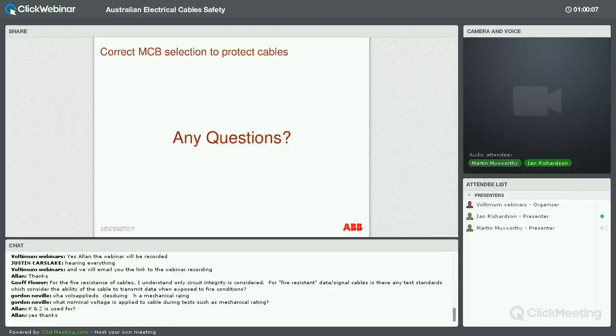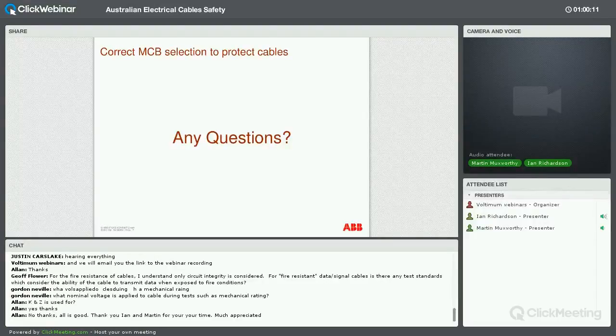Well, people are thinking, Ian, when you were talking about the reduction in life when you increase temperature, there's a rule of thumb that relates to that issue: for every 10 degrees that you increase the operating temperature, and it applies to almost anything, you decrease the life by half. I've actually heard that somewhere else, and I omitted to put it in the presentation, so thanks for that, Martin. That's okay. It's common for cables and a lot of products. I think it's fairly common from an installation breakdown point of view, so it would apply right across.